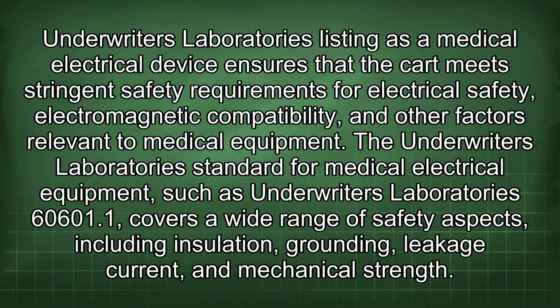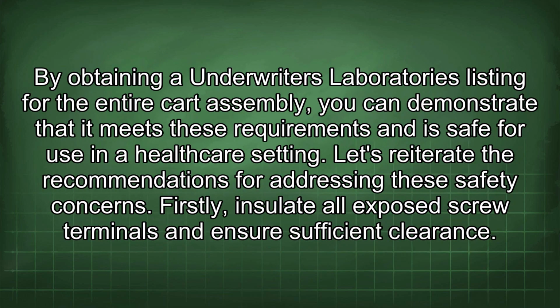Underwriters Laboratories listing as a medical electrical device ensures that the cart meets stringent safety requirements for electrical safety, electromagnetic compatibility, and other factors relevant to medical equipment. The UL standard for medical electrical equipment, such as UL 60601.1, covers a wide range of safety aspects, including insulation, grounding, leakage current, and mechanical strength. By obtaining UL listing for the entire cart assembly, you can demonstrate that it meets these requirements and is safe for use in a healthcare setting.